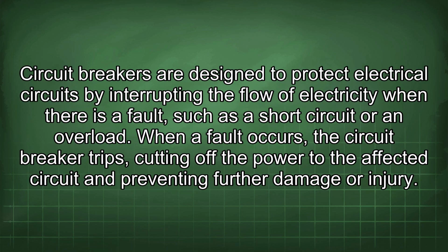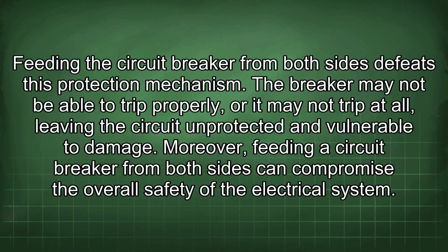Circuit breakers are designed to protect electrical circuits by interrupting the flow of electricity when there is a fault, such as a short circuit or an overload. When a fault occurs, the circuit breaker trips, cutting off the power to the affected circuit and preventing further damage or injury. Feeding the circuit breaker from both sides defeats this protection mechanism.